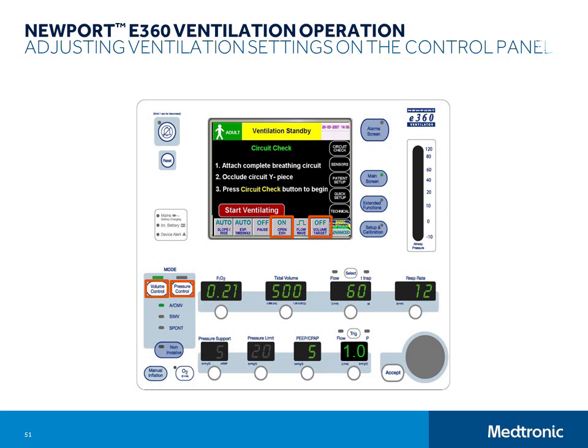You will use the trigger selector, which is found above the numeric display, to select either pressure or flow for triggering. Then press Accept to confirm the selection. After selecting the trigger method, press the button below the numeric value to select the value for adjustment. From this point on, it uses the standard touch turn accept method.